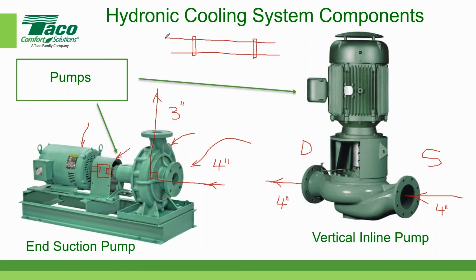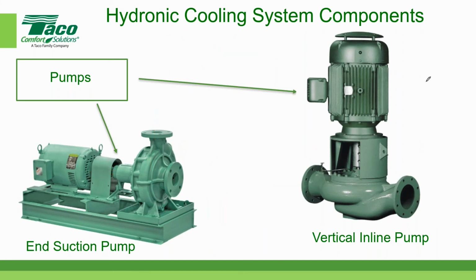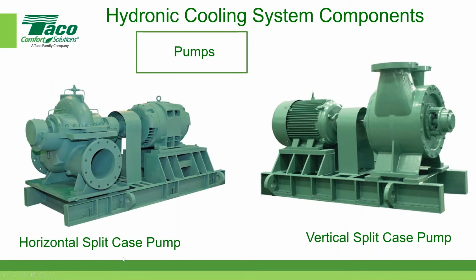Anyway, so if this is our pipe, we can connect the pump in line with the piping by simply cutting the pipe. That's not how you do it in the real world, but you can sort of think of inserting the pump if you cut the section out. So therefore, it's in line with the piping. So those are the two most popular pumps. And for tonight's discussion, I just wanted to also include the other pumps, especially for larger chilled water systems. We have our horizontal split case category of pumps, and these can go up to as high as 15,000 gallons per minute. And then we have our vertical split case. So where do those names come from?